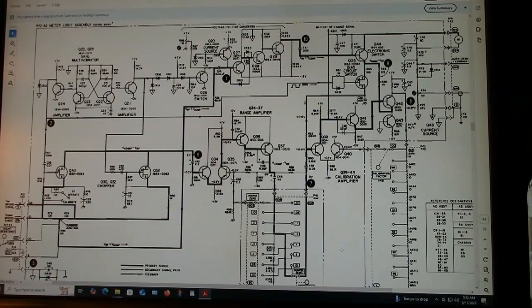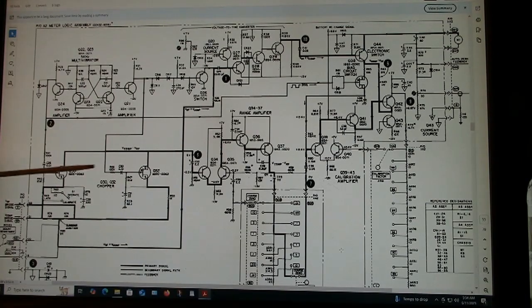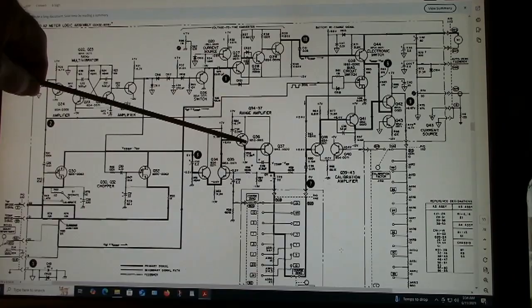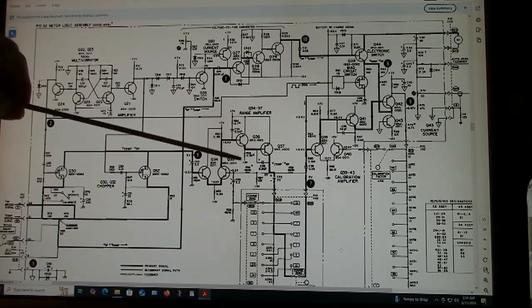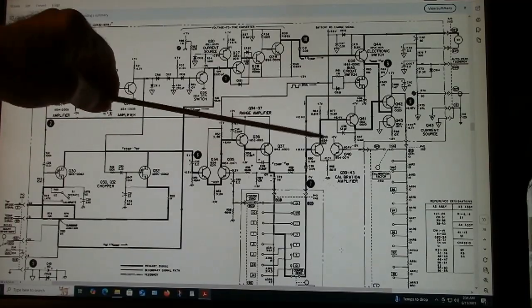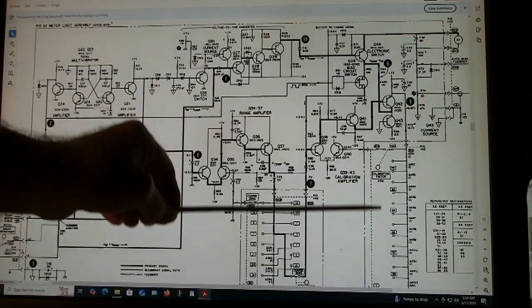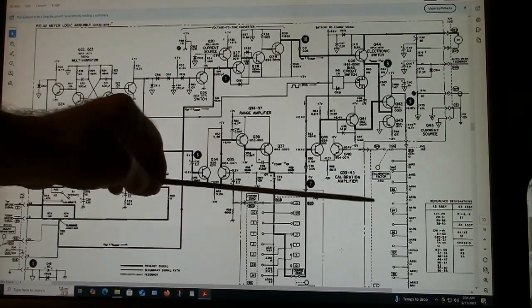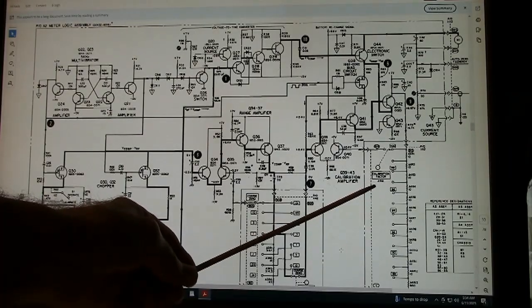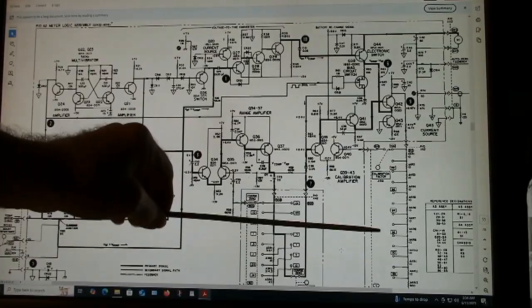It's kind of nice to see where HP isn't using a synchronous motor, incandescent bulbs, and light dependent resistors like some of their earlier devices. But anyway, this signal drives this chopper, and what the chopper does is it produces a square wave signal. The amplitude of that square wave signal is proportional to V comp minus VRF. The output of the chopper is applied to the range amplifier here, and of course you've got your range switches which vary the gain of that circuit, and then that's applied to the calibration amplifier, whose gain is dependent upon these calibration factors, which vary with the calibration factor for the individual thermistor mount that you have. So you've got that adjustment. It's a front panel adjustment here.